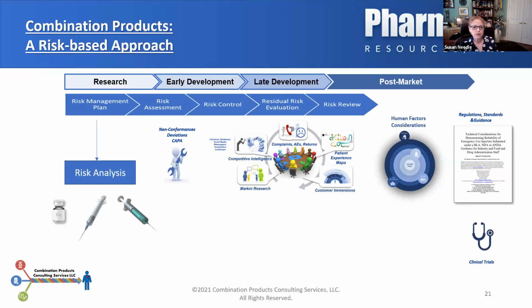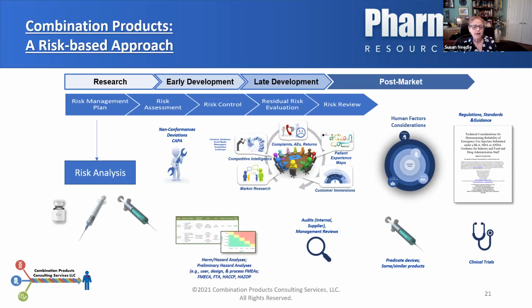Your clinical trials that you have pre-market are a source of information for your risk management. And there's also post-market clinical trial activity that may be happening. And you can use that information to inform your risk assessment. You can look at predicate devices or similar products that may exist in the marketplace to inform your risk assessments. You can use audits as a source of data. Those could be internal audits, supplier audits, health authority audits, or even your management reviews as sources of input relative to your risk management. And ultimately, those basic risk management tools, doing harm hazard assessments, your preliminary hazard analysis, using your user design process FMEAs or user requirements risk assessments, FMECA, failure modes, effects, and criticality analysis for your drug constituent parts, fault tree analyses. You can see there's a whole plethora of different risk tools that are available to you. Have them in your back pocket so that you're applying the appropriate risk tool based on what you need.